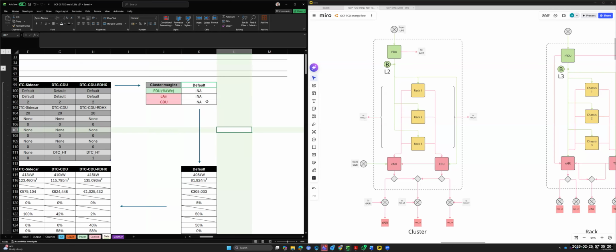It doesn't check whether there's capacity for the non-critical power, because that equipment is driven by the demand rather than sized according to the cluster configuration. And the same goes for the heat rejection unit. The sizing of that is driven by the demand.